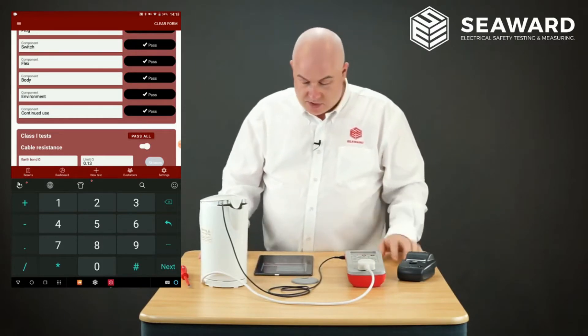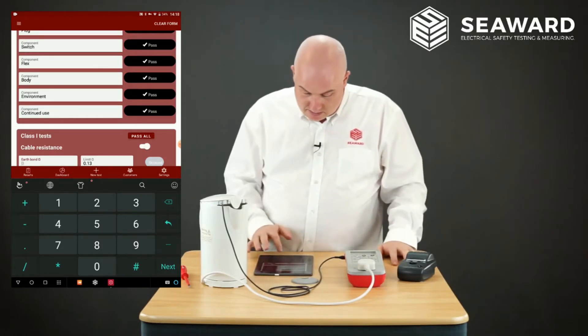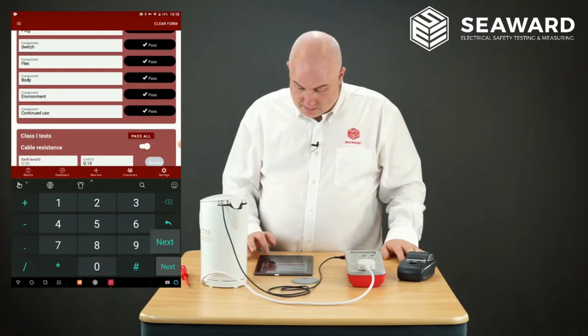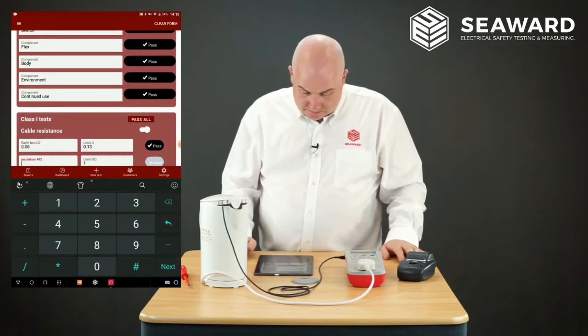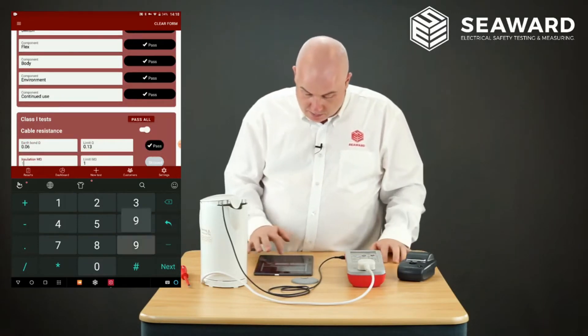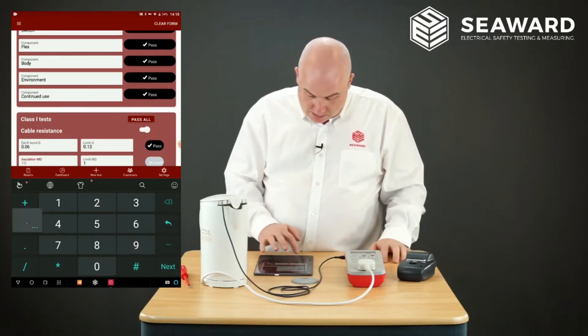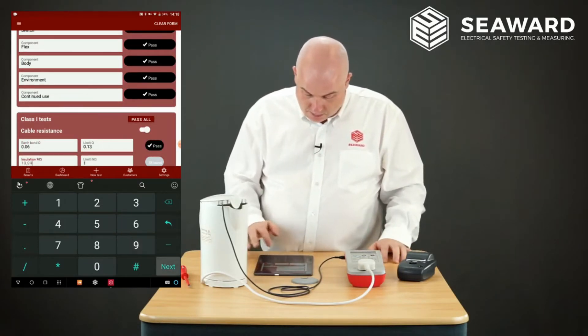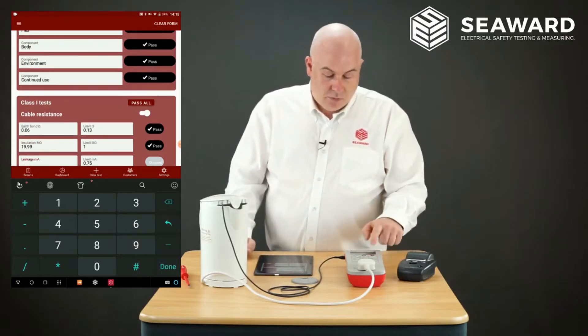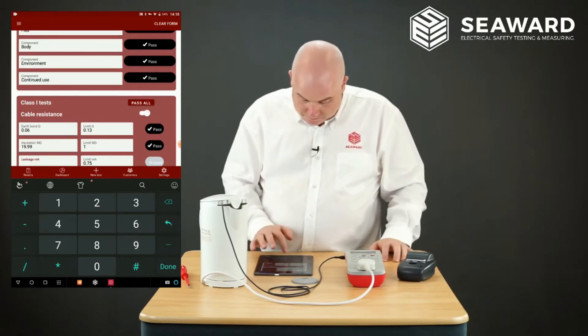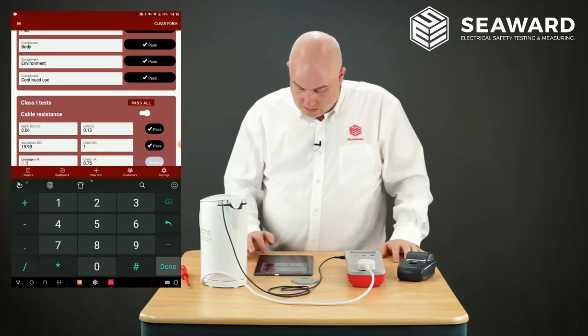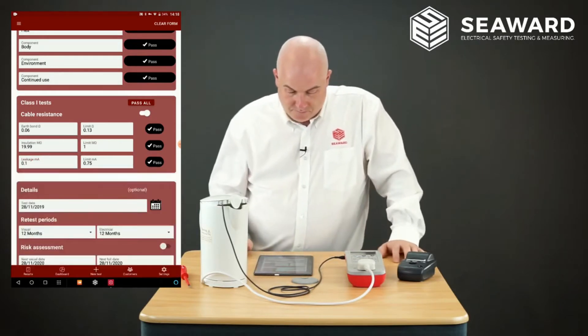The readings are: earth bond 0.06, insulation 19.99 megaohms, and leakage 0.10 milliamps. I enter each value and press Next, then Done.